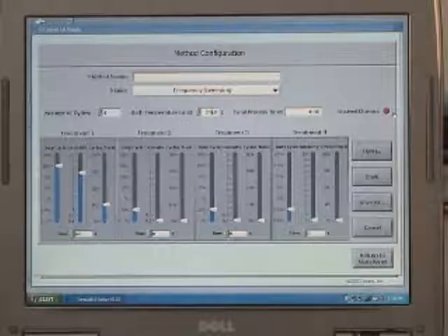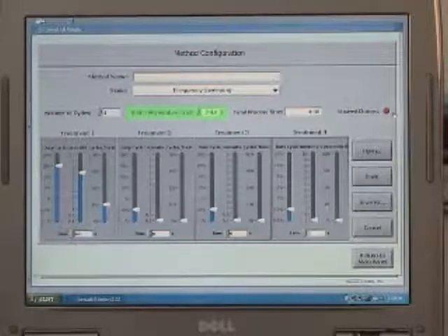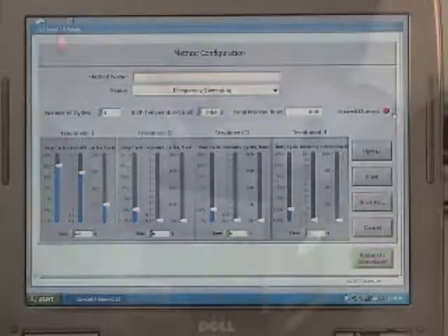For more time, additional treatments can be added and/or the number of cycles can be increased. The cycle number is how many times the programmed treatments will be repeated during the running of a method. Bath temperature limit sets the maximum temperature for the water bath. If this temperature is reached during a method, the instrument will stop. The return button returns to the main panel and does not save a method.